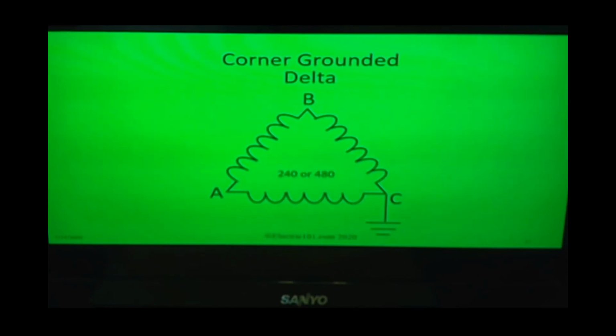Now, one transformer you've got to be aware of is this guy, and it'll get you right there. It's called a corner grounded delta. You see these in buildings that were built around World War I and World War II. So we're talking about older systems. Back in those eras, there was a shortage of copper, and all the copper went to make bullets. So any buildings built during that time used the building steel itself as a conductor. So this is where you take C phase and connect it directly to the building steel. And this energizes the building.